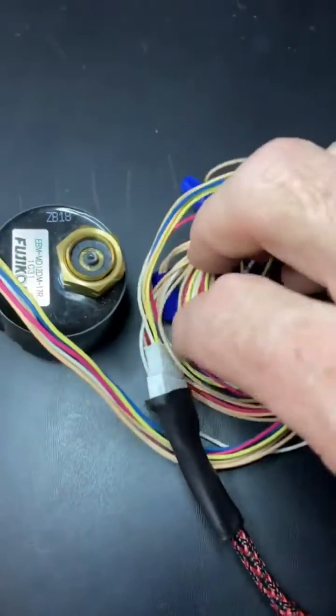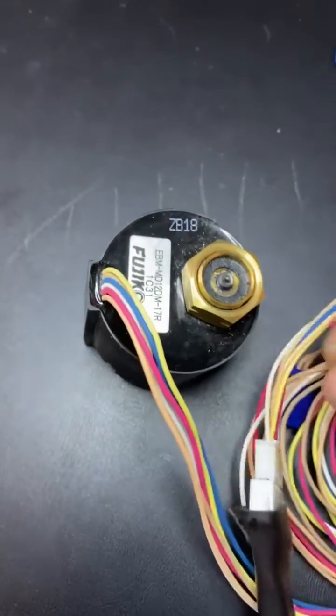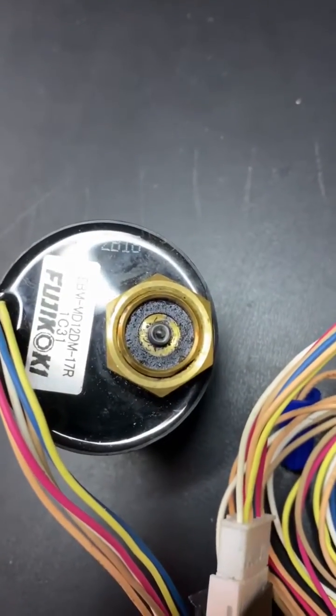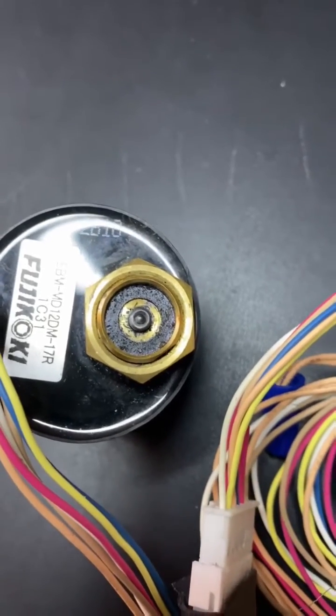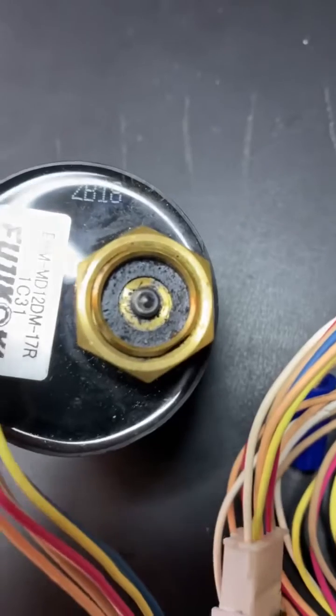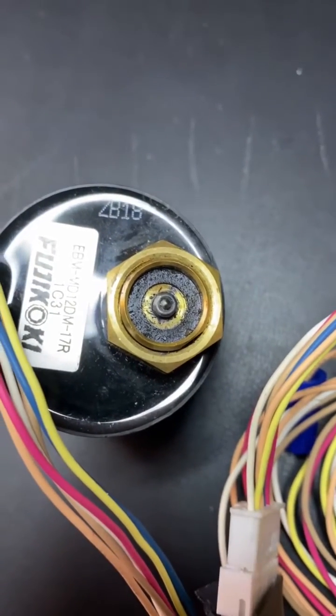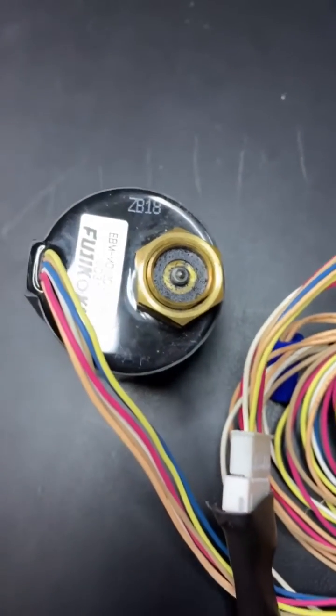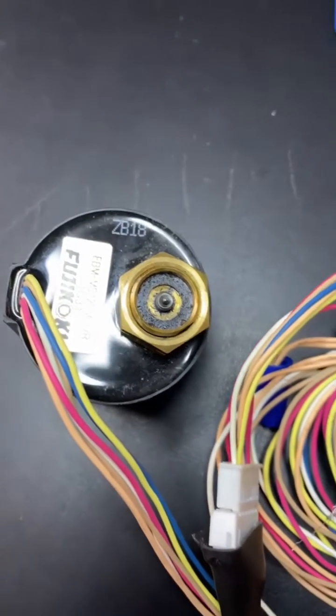This valve we have cut, and I'm going to separate this one winding. As you can tell, the valve is loud, but it still drives in turbo mode. And now this is in regular mode — notice how it is not moving at all. But if you weren't sitting right next to it, you might not be able to tell that that's what's actually happening.